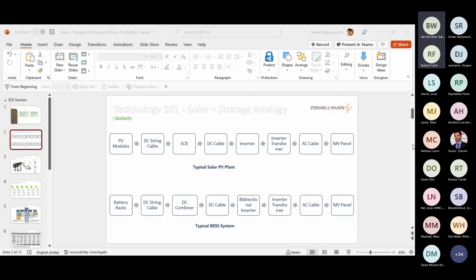Cool, and then just maybe around round trip efficiency, the efficiency from AC to AC, or I'm not sure if you do it DC to DC. I'll give you a rough idea: the efficiency from AC to AC, meaning taking power from the grid, charging the batteries, and discharging the entire power back into the grid, is approximately 85 to 86%.